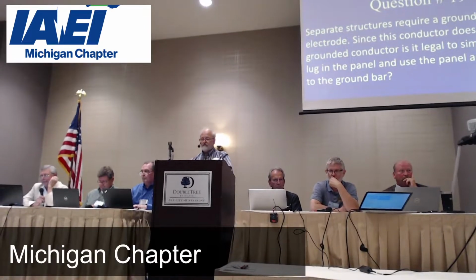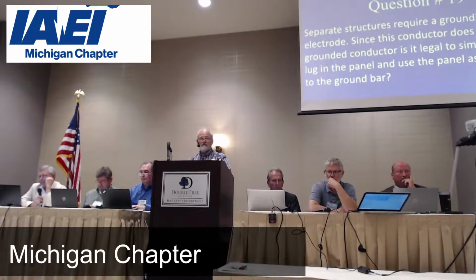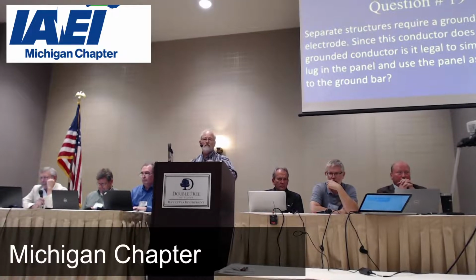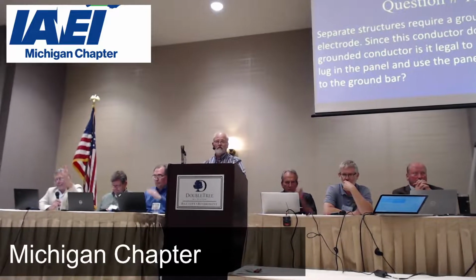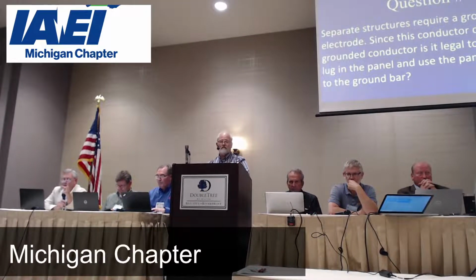It depends. So if the fault current's coming from the equipment, it's equipment grounding using the conduit system, boxes and other fittings. But system grounding is trying to defer lightning strikes and incidental contact from the utility. System grounding, as it's defined in the code, means that I have a normally current carrying conductor that is bonded to the earth and to the grounding system. I mean, it's a Y connected system, or it's a midpoint grounded like a residential. System grounded means my system that I'm using to operate equipment is connected to earth.